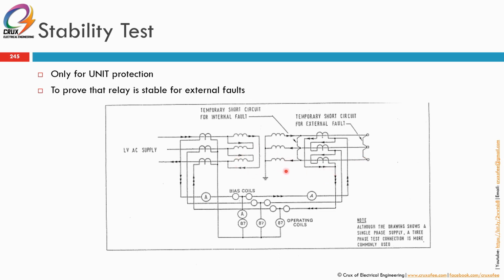So if you are using this for REF, for example, if there's an REF with one additional CT here to be summed between these three CTs and this REF, you must also do the stability test for the REF CT here. Because with the REF CT, you will only know whether the direction is correct when there's a fault. So the problem would be that when there's an external fault, your REF is triggered because the CT here is connected in the reverse direction.